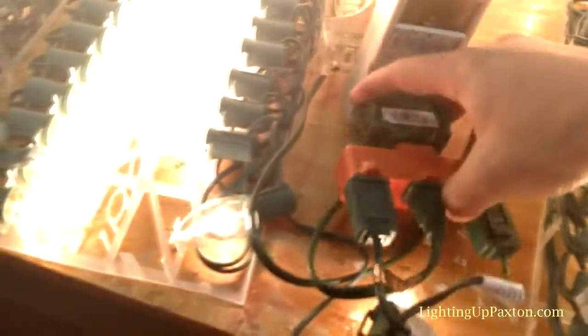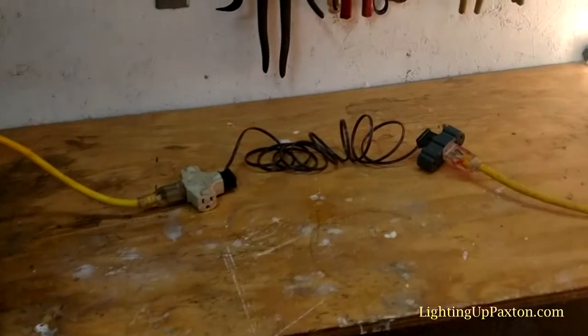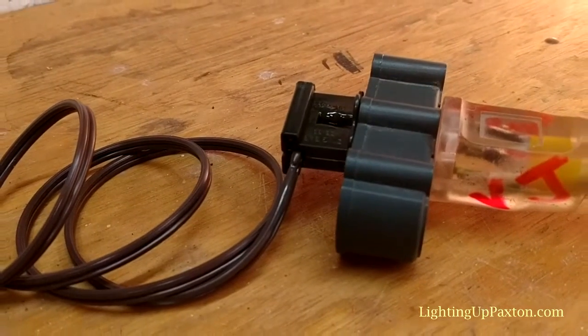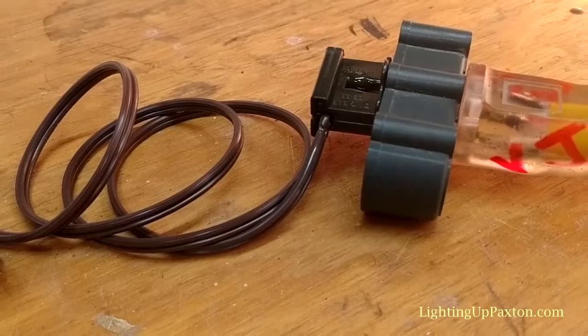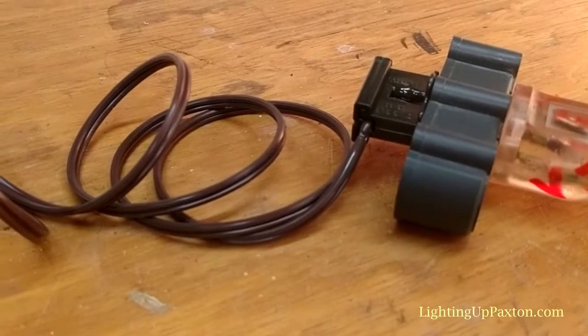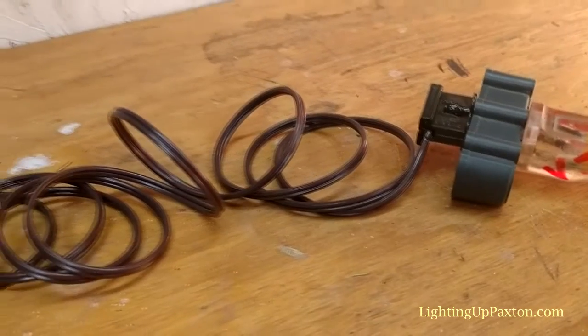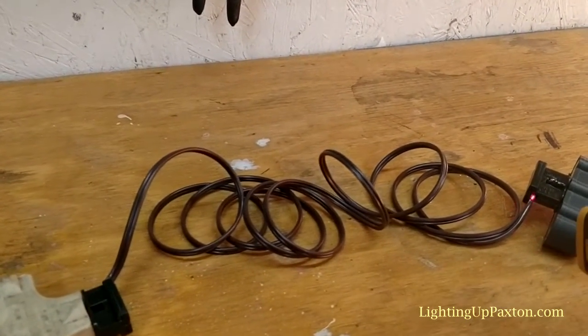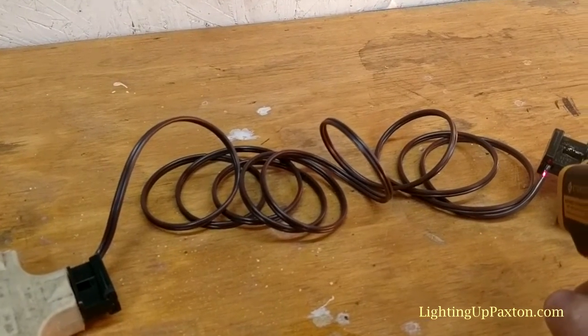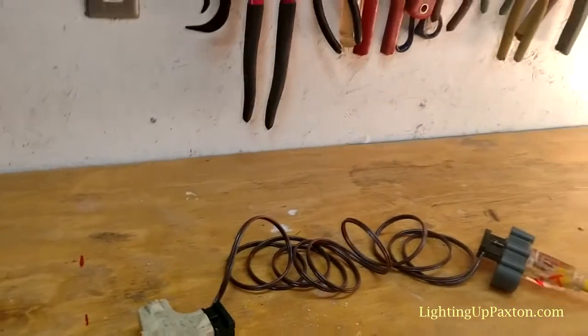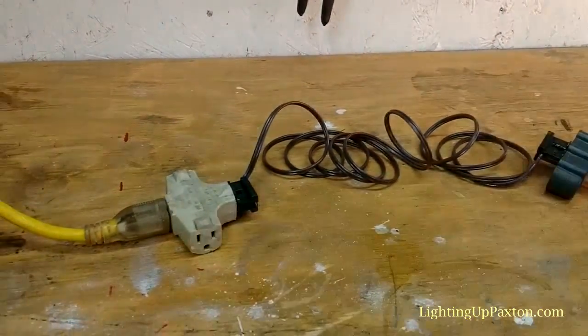Ready, set, here it goes. Three, two, one, there they are. I don't know if the camera can see that but that is a vampire plug that is beginning to melt. Oh my gosh, and the wire's melting right there too. We're going to have catastrophic failure here soon. Look at that wire melting right where it enters the plug and the plug itself is melting. Down to 107 volts, started at 123. Temperature - oh my gosh - 180 plus! I can get it right on this spot - 199! There it is!